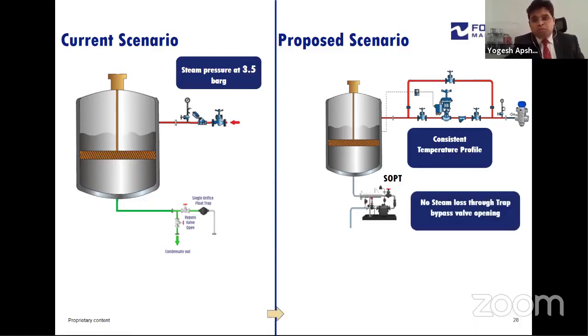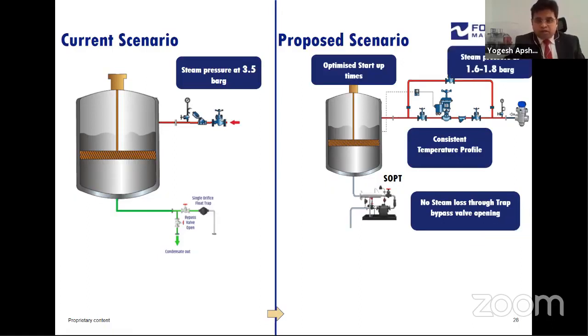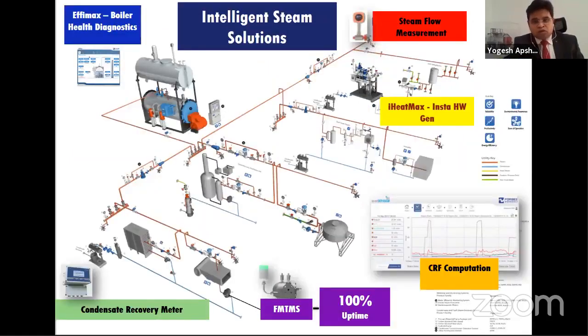Then steam operated pumping traps, which will ensure the condensate recovery back to the feed water tank. There is no problem in the stalling conditions. Then optimize startup times, and the steam pressure, which we can regulate at 1.6 bar or 1.8 bar. So these are the recommended solutions for this. So coming back to our earlier slide, how can we make the complete steam system intelligent? What are the typical aspects of these intelligent steam systems, considering right from the boiler back to the condensate recovery system?